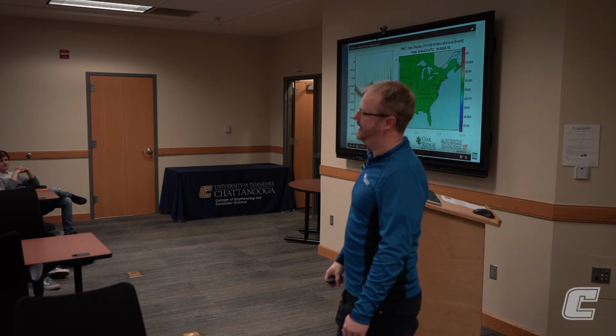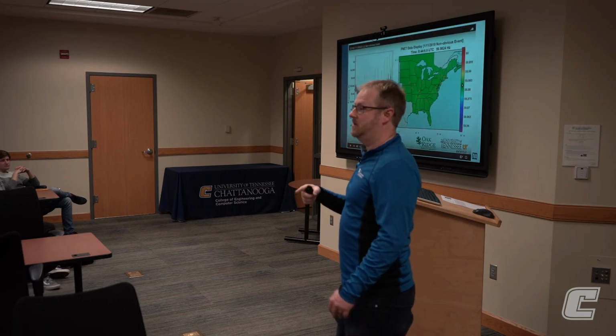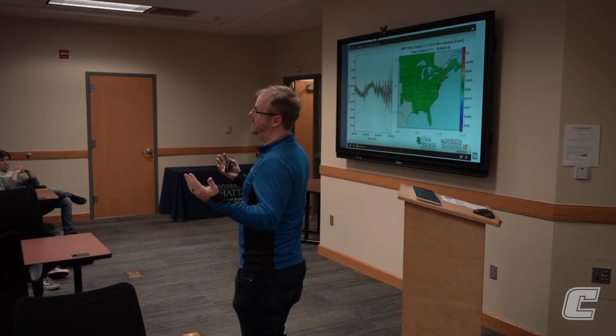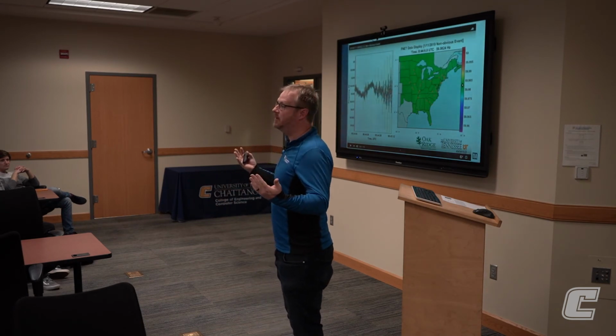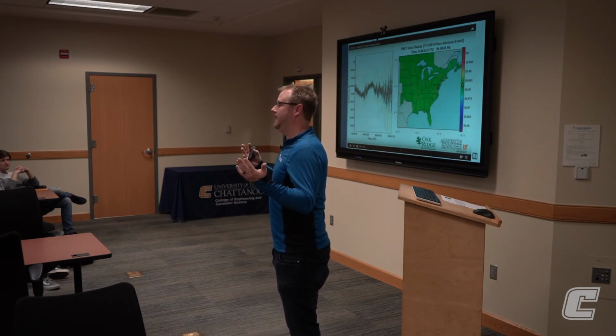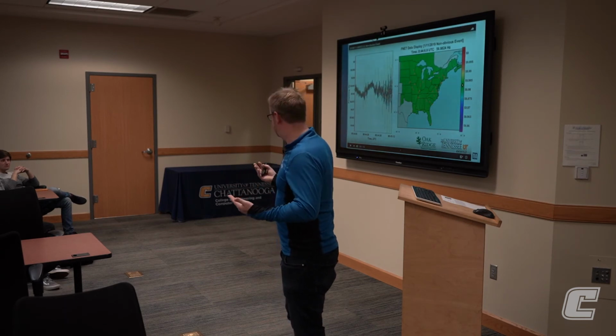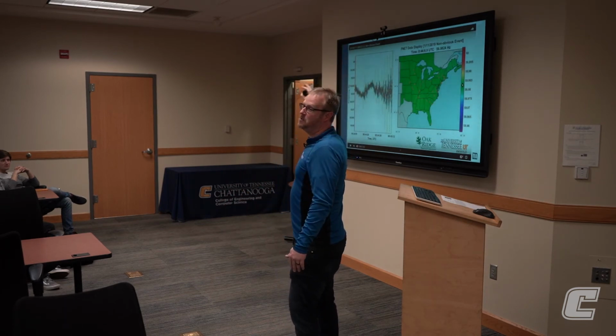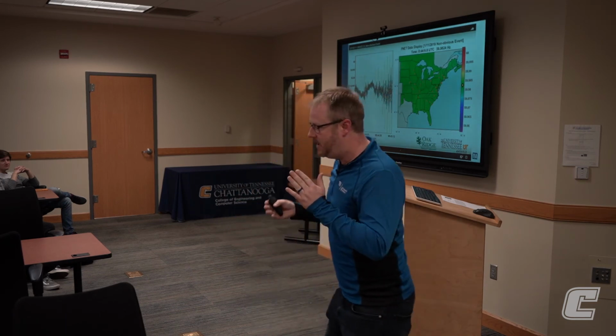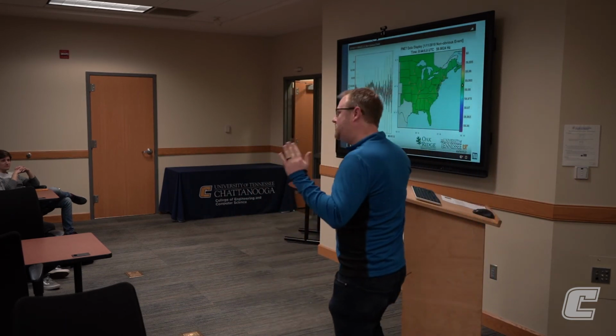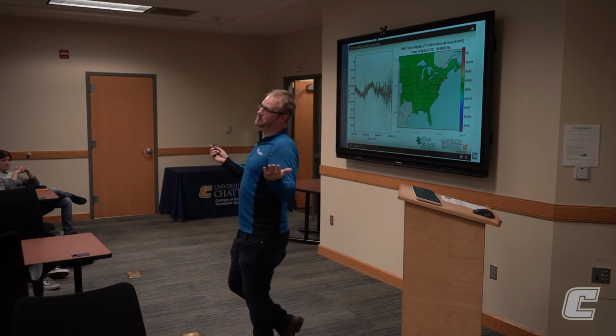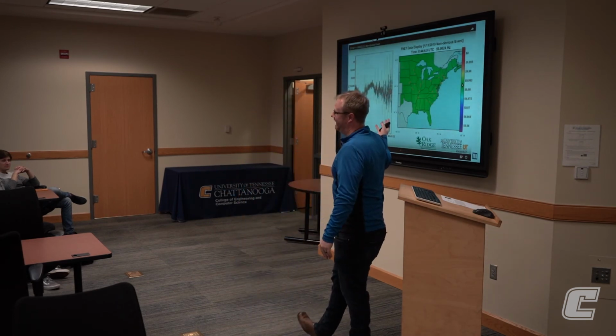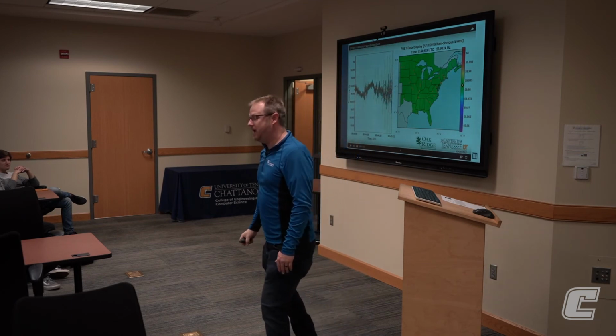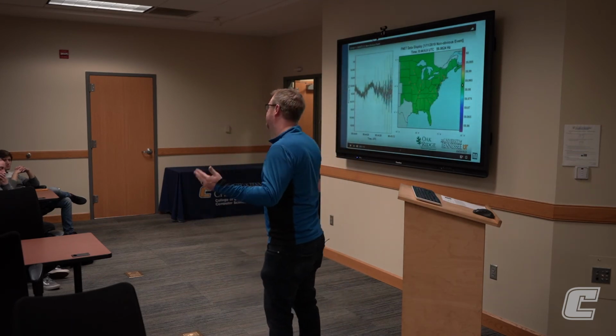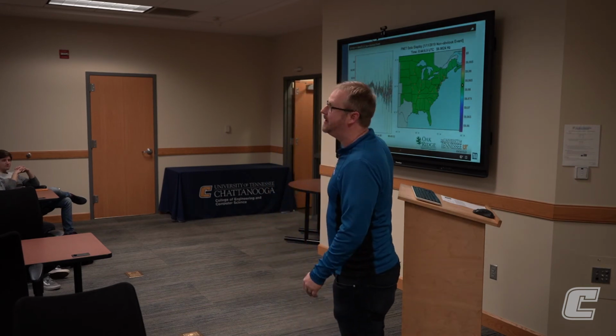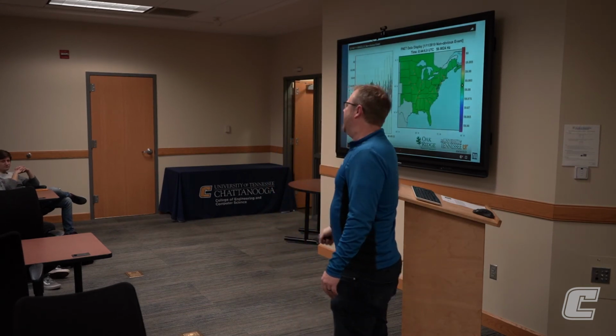You know, and turns out when they tripped the unit, because they were having so much trouble controlling it, because they didn't know at the time that that voltage signal had dropped and that their controller was going haywire. But when they tripped the unit, manually tripped it, all of this went away. So we were able to go back and say, when did you trip the unit? Here's the oscillation times. You know, when did you start experiencing problems? Because they knew they were having problems. They just didn't know they were shaking the grid. And so we were able to go through several days after and piece all that together. It's scary.